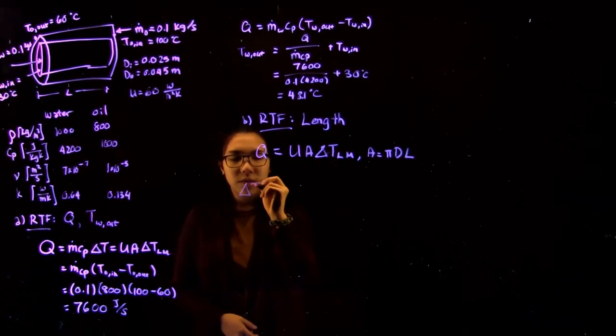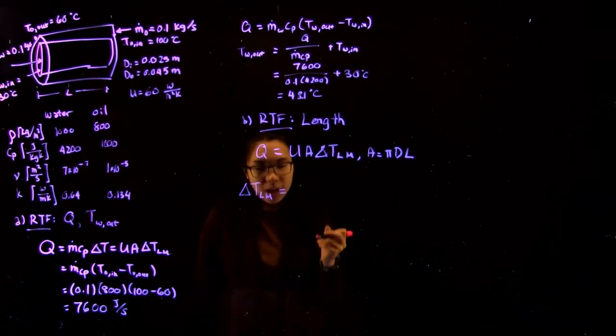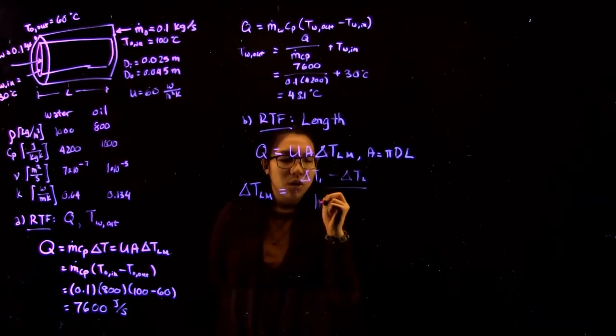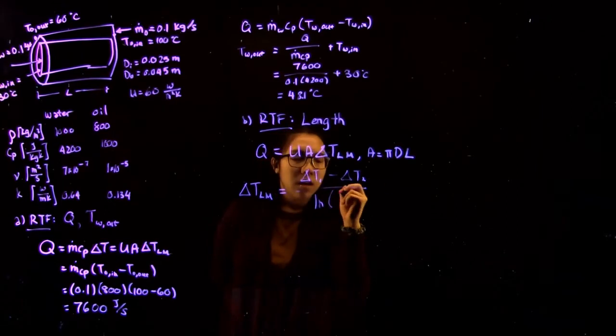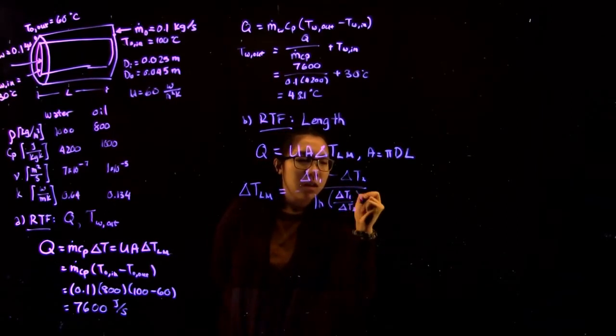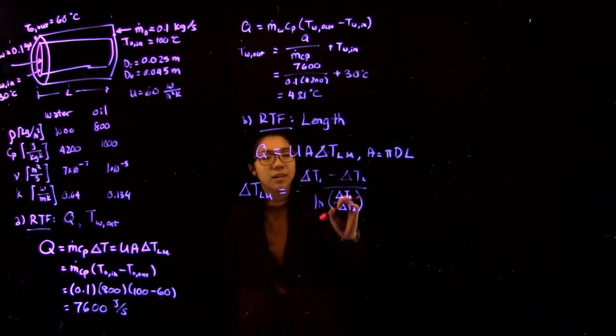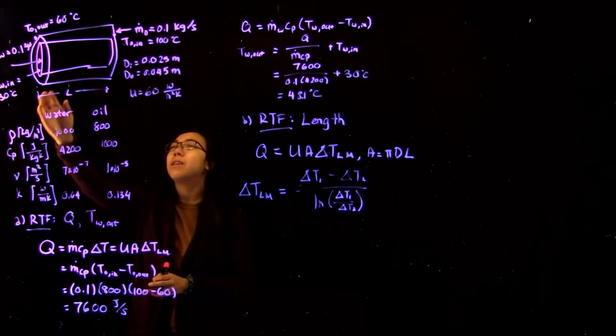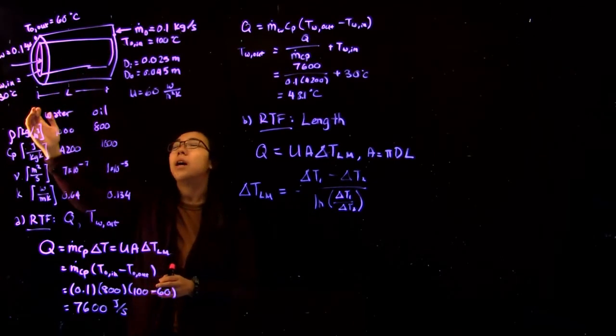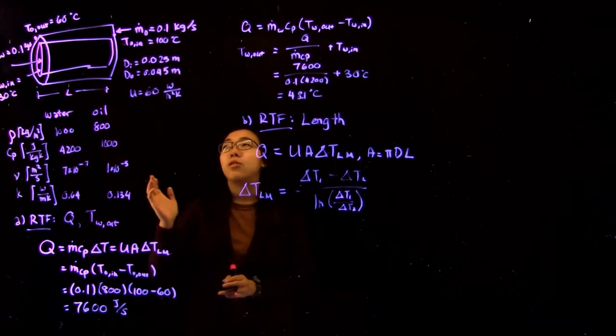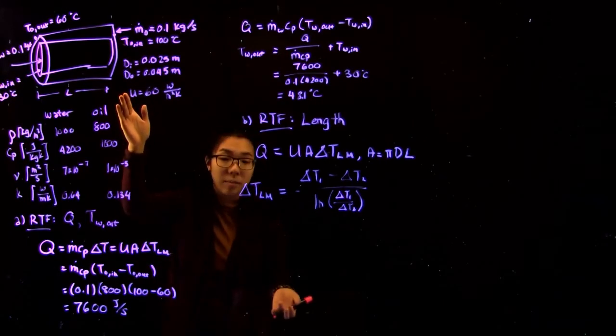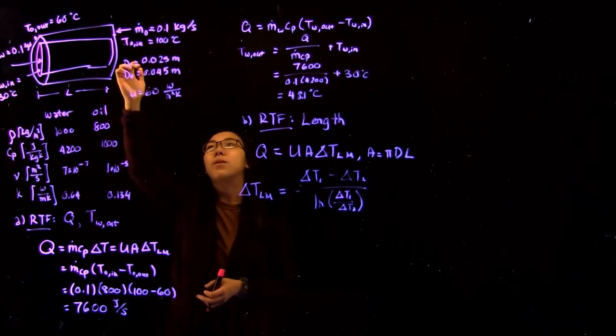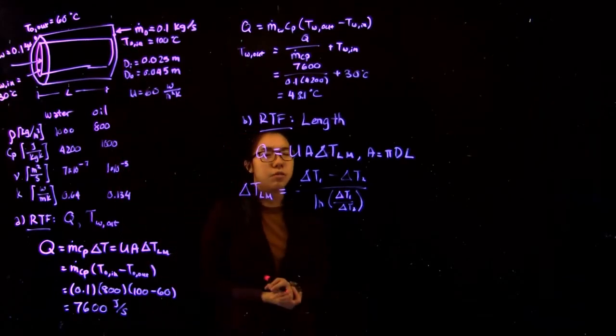So what we want to do is find the log mean temperature, which is equal to delta T1 minus delta T2 over ln of the ratio of these. In this case, delta T1 is whatever the temperature difference is on one side of the exchanger. So in this case, it would be the difference between the oil out and the water in. Delta T2 similarly is the change in temperature or difference in temperature on the other side of the exchanger, which is the difference between the oil in and the water out for counter-current flow.